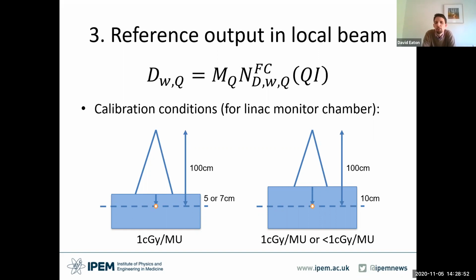But calibrating to 1 centigray per monitor unit at 10 deep can involve changing the output of the machine quite substantially. And some manufacturers are more or less reluctant to do this. So there's certainly one center who've taken the approach of choosing a calibration value which is less than 1 centigray per monitor unit. So for example, 0.83 per MU at 10 centimeters deep gives you a result for a fixed SSD setup at Dmax very close to 1 centigray per monitor unit. So that the change in your absolute output from the machine is going to be minimal. Now it's fair to say that's also true if you do isocentric at 5 deep because they sort of cancel out.